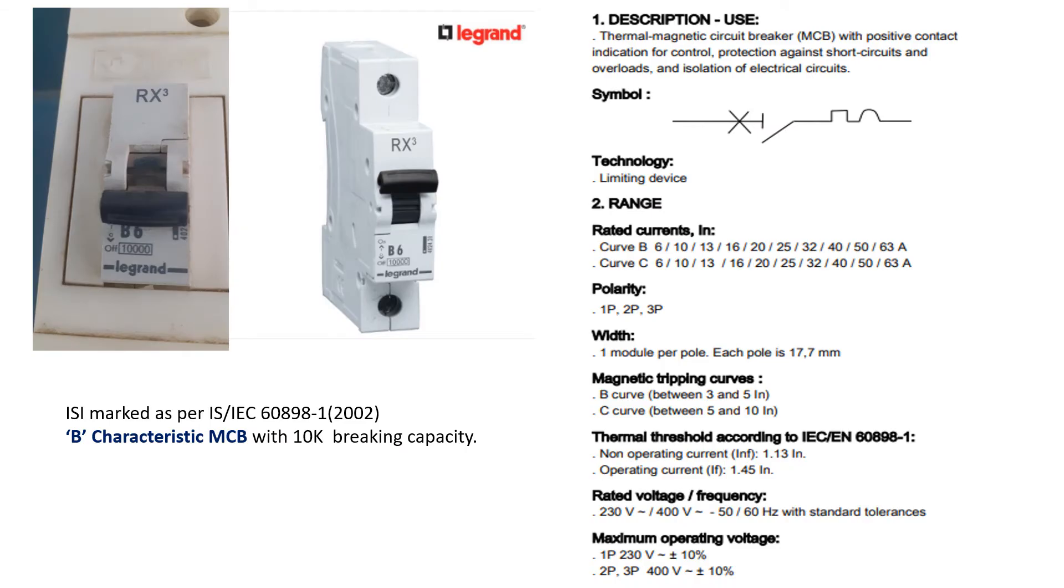Before conducting actual experiment I would like to introduce few basic things related to this MCB. Now this is single pole MCB which we are having on our testing kit. Actually how it looks this is produced manufactured by Legrand company. Its code is RX3 and in its description you will find lot of things. Actually it is B characteristic MCB, here B6 is shown. So this B indicates it is a B characteristic MCB with 10k breaking capacity. So here you will find 10,000 so that is 10k so its breaking capacity is 10k which is mentioned here only.